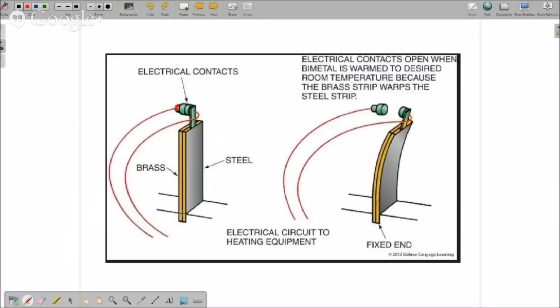And we have a bimetal strip that's fixed on one side. And what happens when you have two different types of metals, they expand at different rates based on temperature. So when the temperature changes from its designed closed contact position and temperature, as the temperature changes, let's say it's warmed up and it's getting hotter and hotter. This bimetal strip begins to warp.